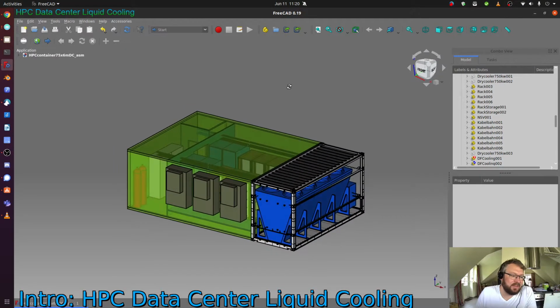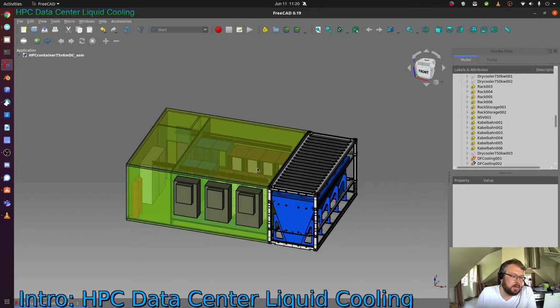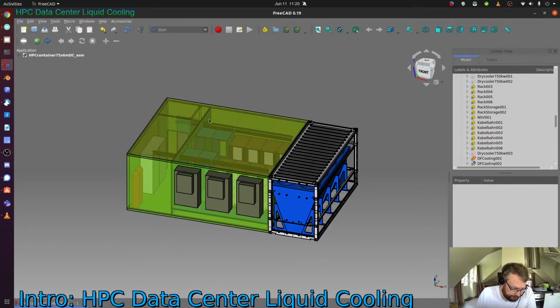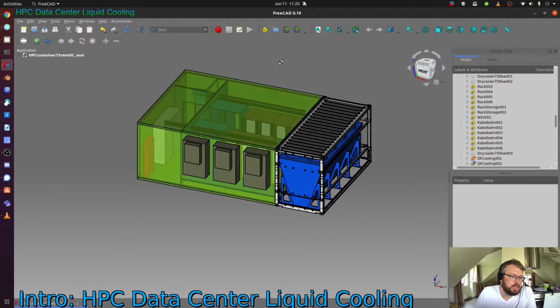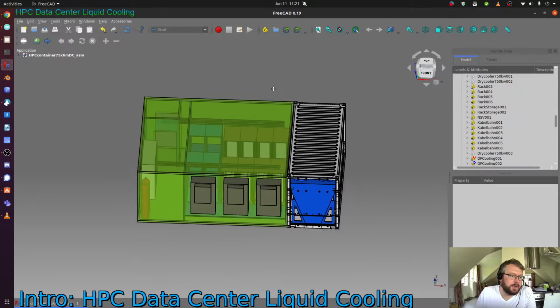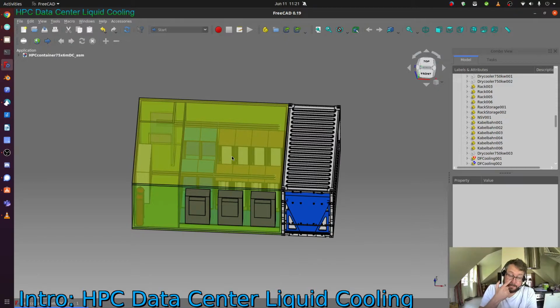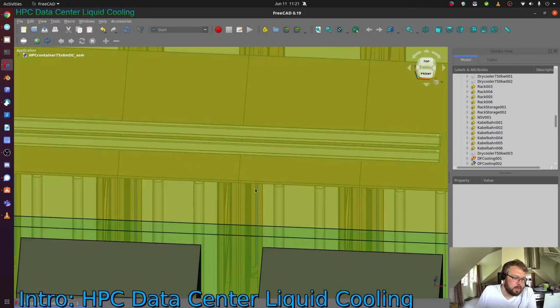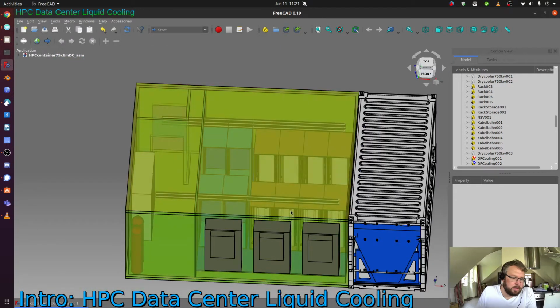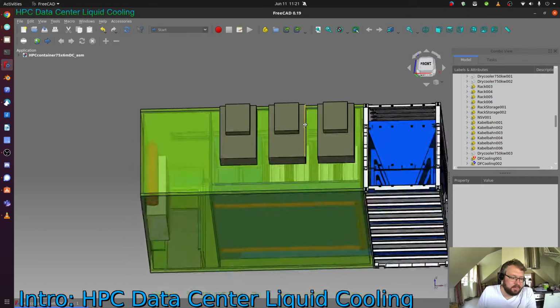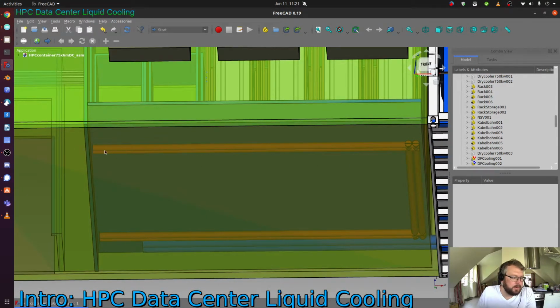We're talking about a total of 750 up to 800 kilowatts of cooling gear, and this is achieved in a relatively compact space, because due to liquid cooling you have very, very high energy density per rack. This is up to 84 kilowatts per rack. As you can see, we have 8 ComputeRacks that have a dummy inside here. This is the piping connecting the servers with the direct water cooling and moving the water temperatures into the raised floor. This needs a raised floor not to move the air, but rather to have space for the piping.